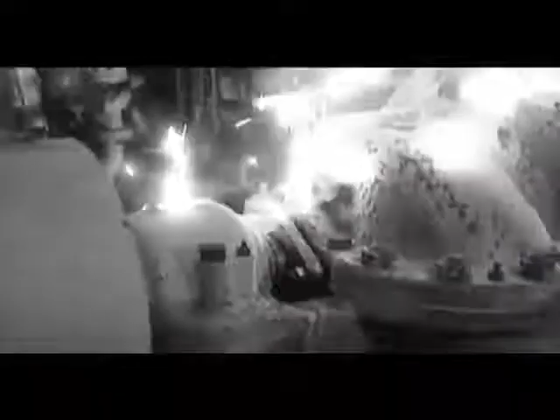The initial explosion, if that's all that would have happened, we probably would have been okay. But unfortunately, the initial explosion appears to have fractured the main oil line in the B module. And that contributed a large amount of fuel to the fire. Crude oil happens to burn with a very thick black smoke, and that dense smoke basically rendered that entire deck uninhabitable very quickly. With the smoke making helicopter evacuation impossible, workers trapped above the burning production module had no good way to escape. So you've got to find your way in dense, dark clouds of black smoke in the middle of the night, find a rope, and crawl 10 stories down and drop into 40-degree water and survive.